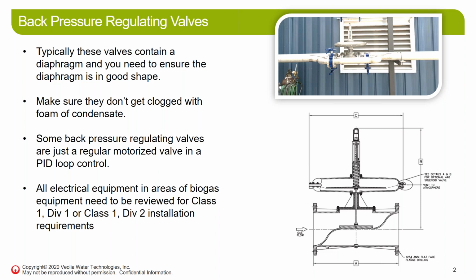A note on electrical classification: make sure all your electrical equipment in areas of biogas is reviewed for Class 1 Div 1 or Class 1 Div 2 installation requirements. Typically seal-offs are required. The right-rated pieces of equipment, NEMA 7 explosion-proof equipment, are needed in areas of biogas equipment. So always make sure that you have the proper electrical installation.